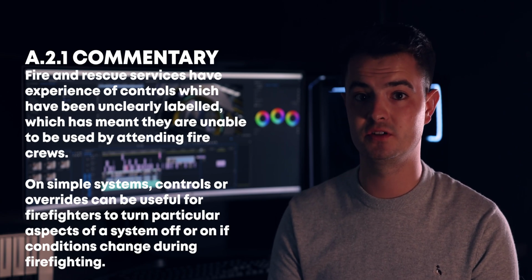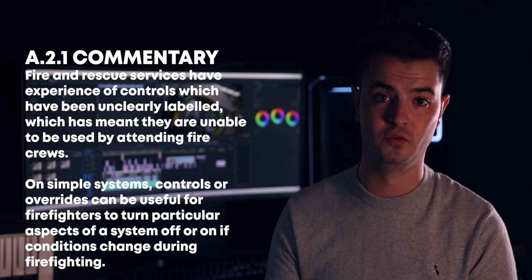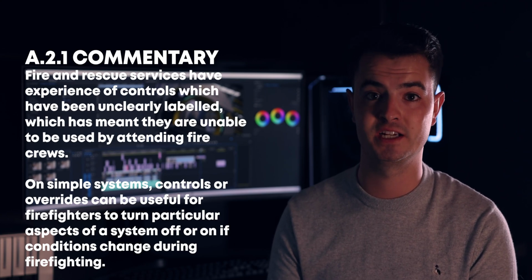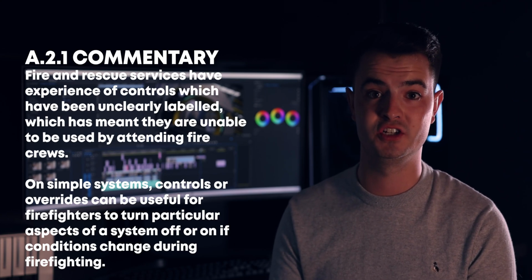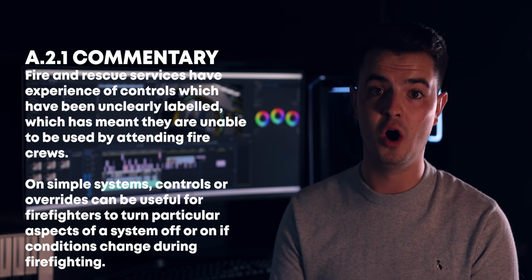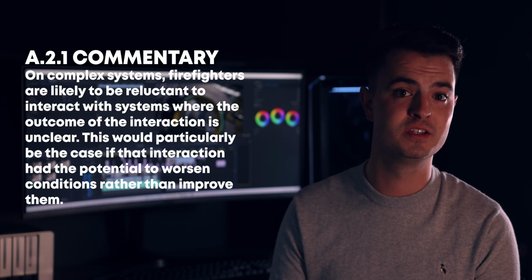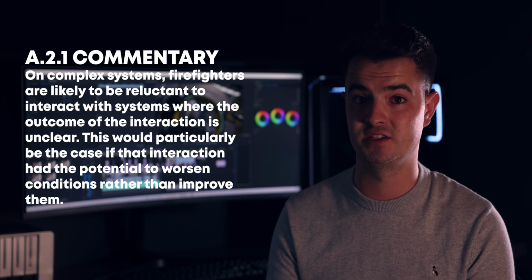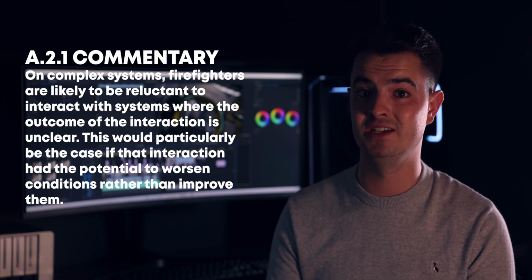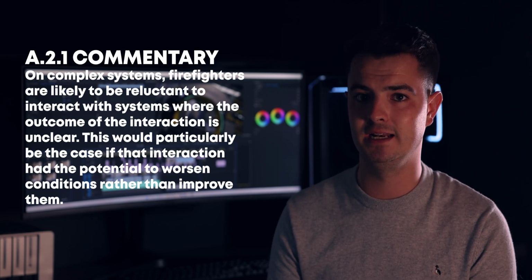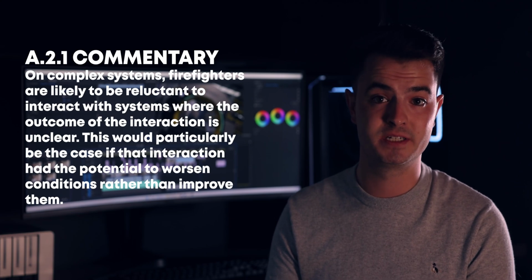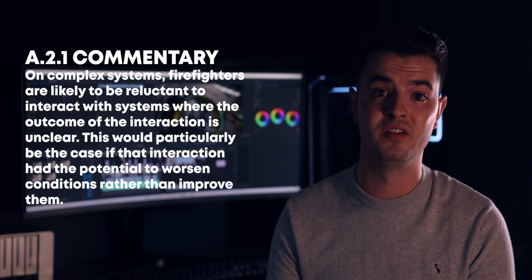On simple systems, controls or overrides can be useful for firefighters to turn particular aspects of a system off or on if conditions change during firefighting. On complex systems, firefighters are likely to be reluctant to interact with the systems where the outcome of the interaction is unclear. This would be particularly the case if that interaction had the potential to worsen conditions rather than improve them. This initial part of commentary then goes on to colour everything that is said about control systems.